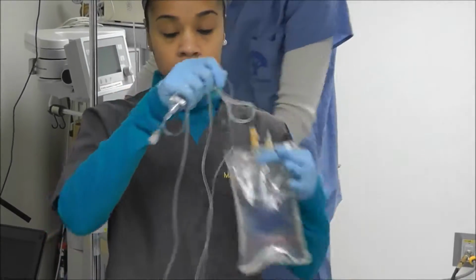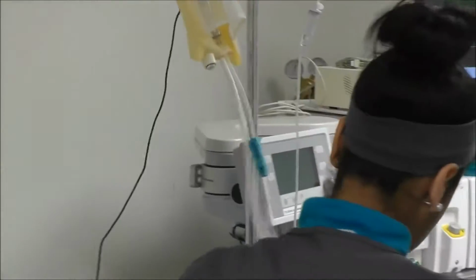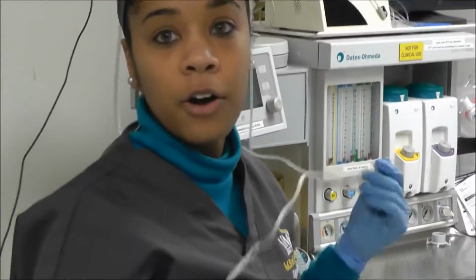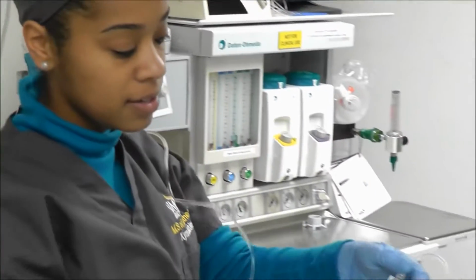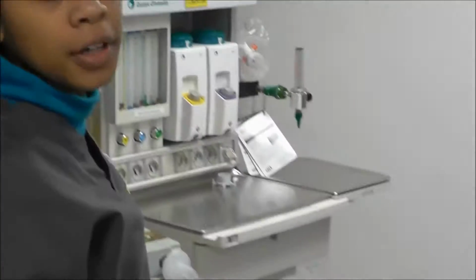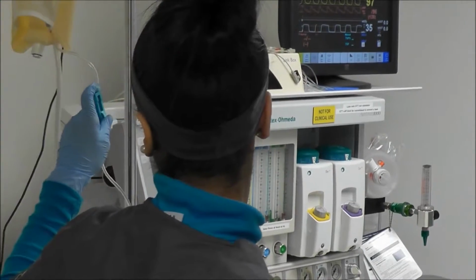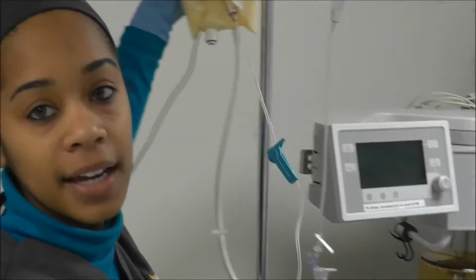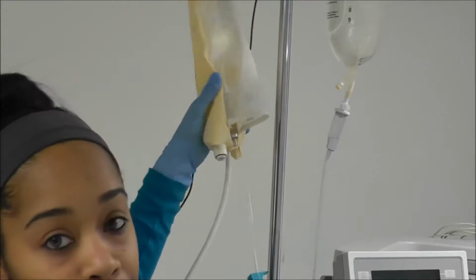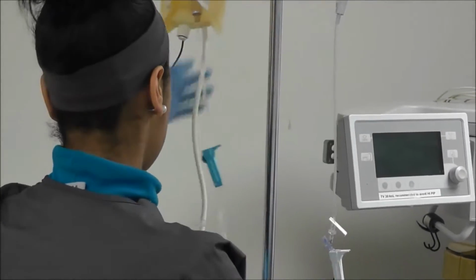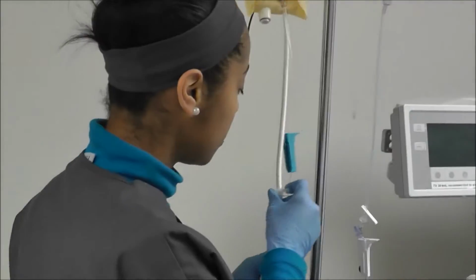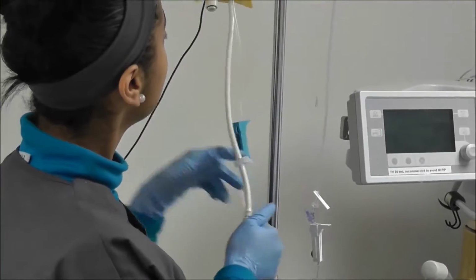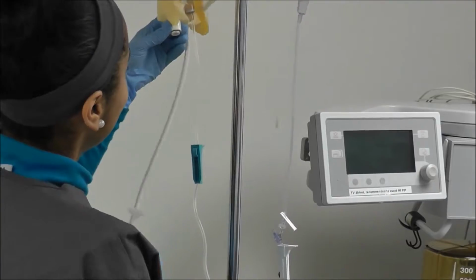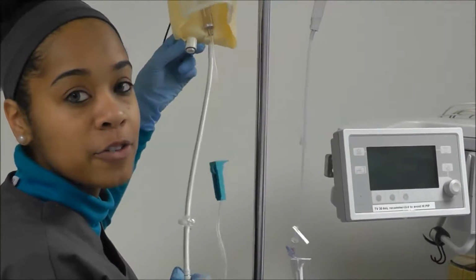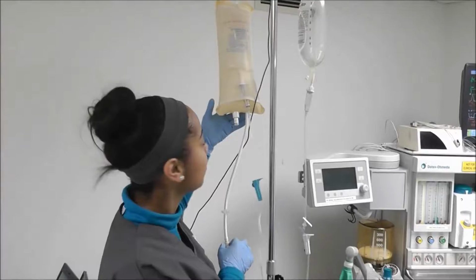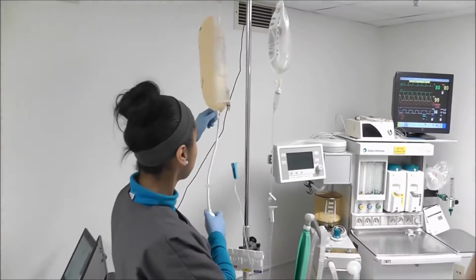First thing you want to make sure you do is flush your tubing. Alright. First thing you want to make sure is that all your stopcocks are turned on in the right spots and that your roller clamp is open. This bag has to be pressurized. So first you want to blow up your pressure bag. Alright, stopcocks in the right spot. You want to pressurize to about 250 to 300. We're at 300. There's a green line that lets you know it is 300.